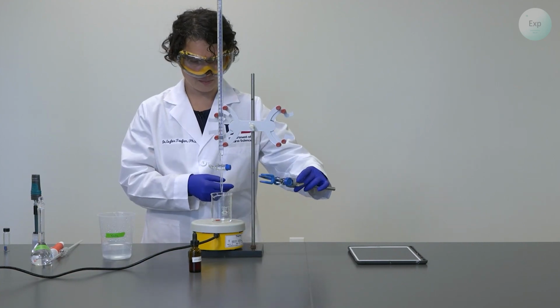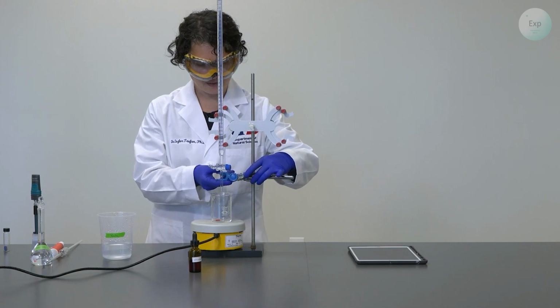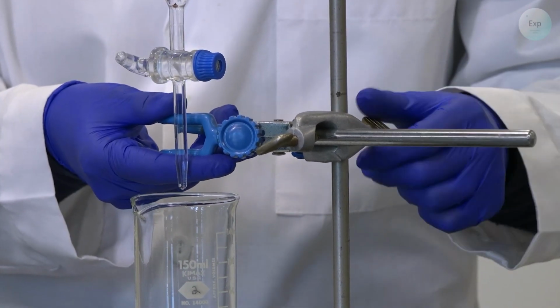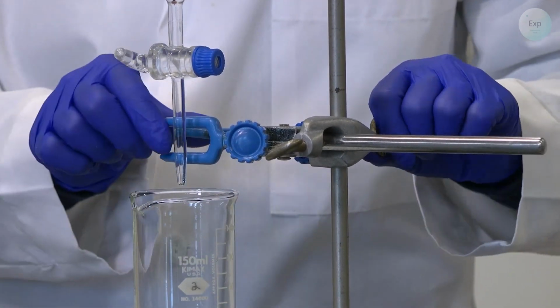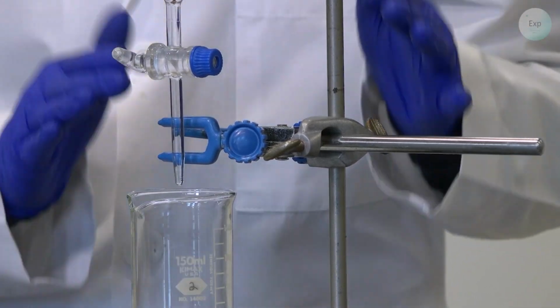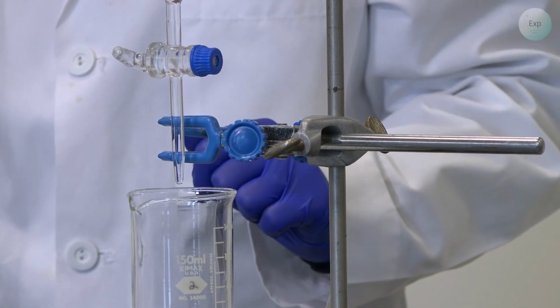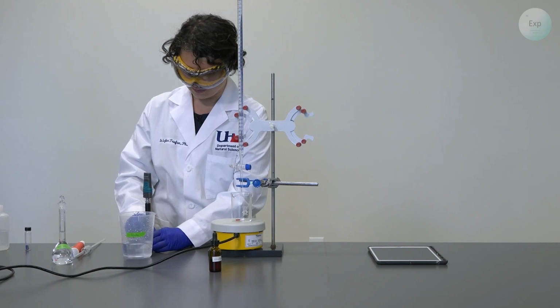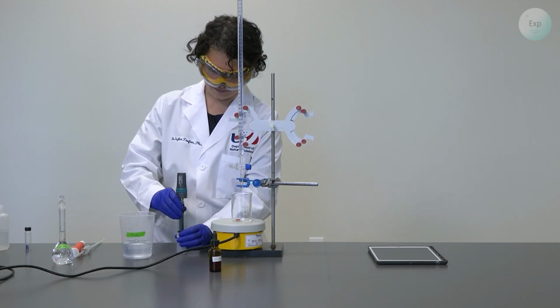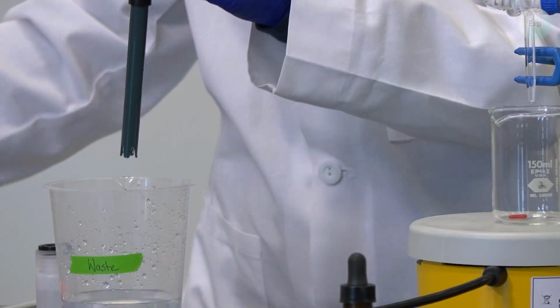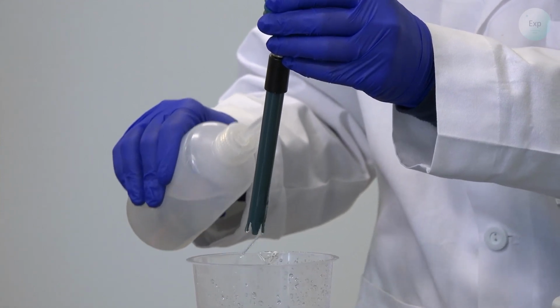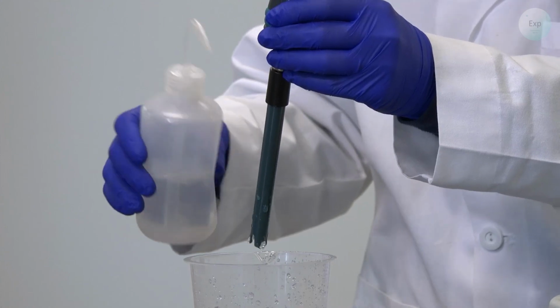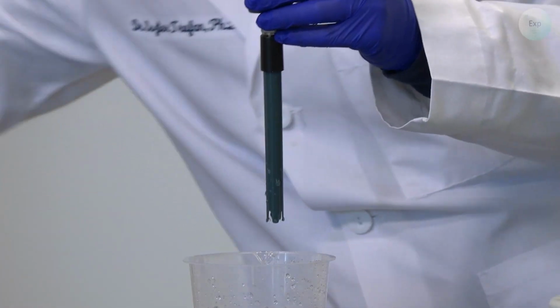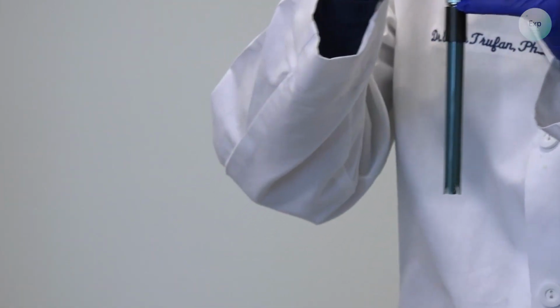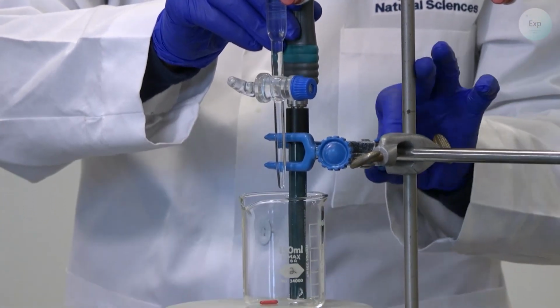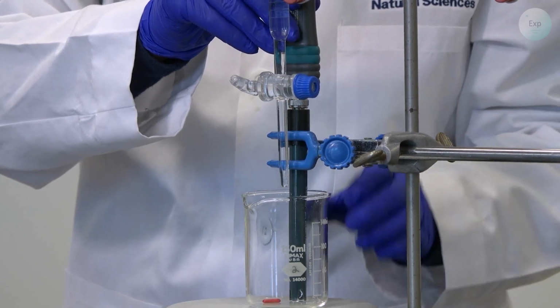The first thing is we approximate the position of our pH probe and we bring our clamp in. The position of the clamps should not interfere with the rotation of the stopcock that is attached to the burette. So that means either positioning it above or below the stopcock for ease of handling. Then we're going to take our pH probe, slightly unscrew the cap of the container, extract it, rinse it with deionized water, wipe it with Kimwipes and not paper towels, and slide it in position, and then loosely close the clamp around it.